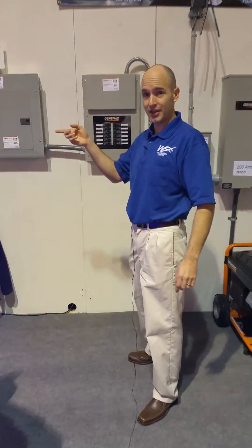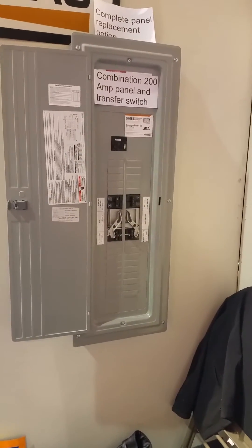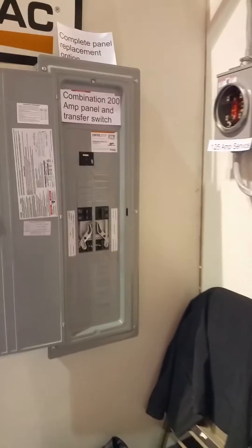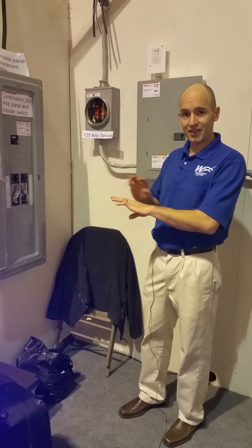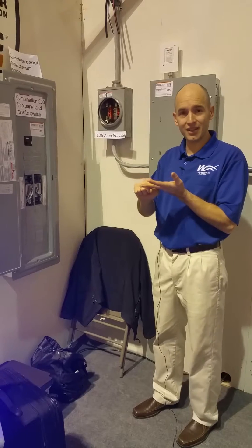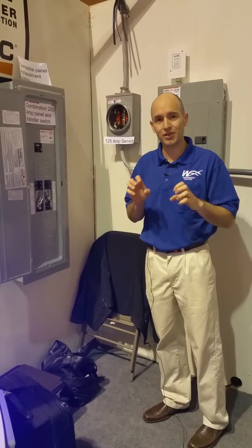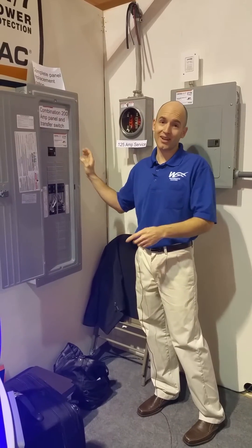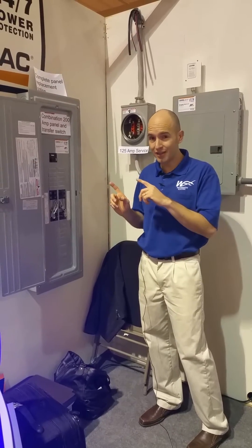The first is the Generac Load Center, and as you can see at the top here, it's a complete panel replacement option. We don't install this all the time, but in some cases it can make great sense — really great when you have a Federal Pacific or a Zinsco panel. You can take the old service panel, remove it — it's old and generally not safe, as Federal Pacific and Zinsco is a breaker design that just doesn't function and work very well. You can put in something that's new, safe, and reliable, and it also has the ability to automatically connect your standby generator to your home in case of an emergency.